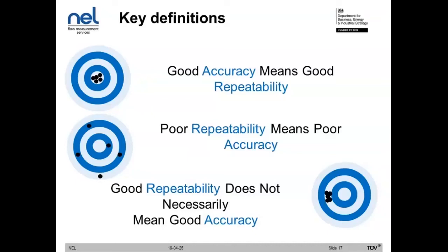On the other hand, it's possible to have good repeatability but poor accuracy. This is what happens when you have a very consistent performance from the measuring device, but it isn't accurate. So there could be an offset or a systematic bias that is affecting the reading of the device. This can sometimes still be useful though, because with repeatable measurements, you can at least determine if the system is changing or not. So there is some value in repeatability even if you don't have accuracy.